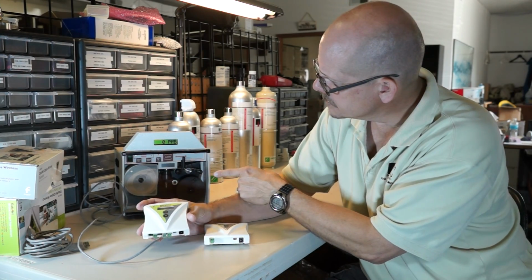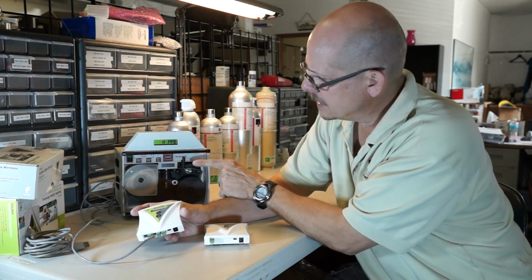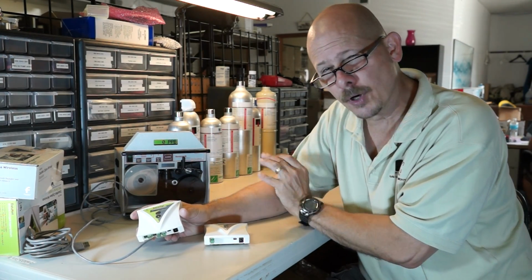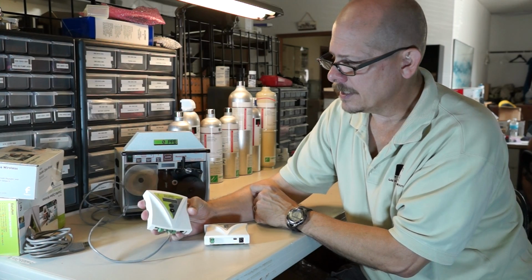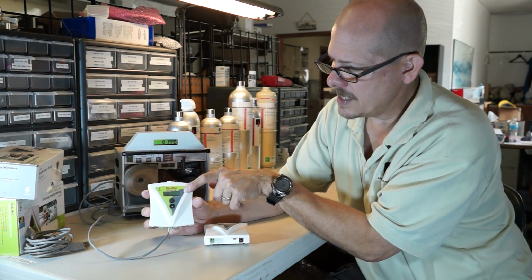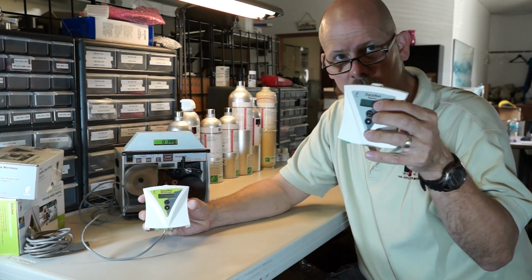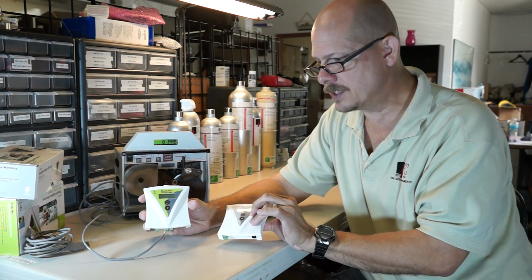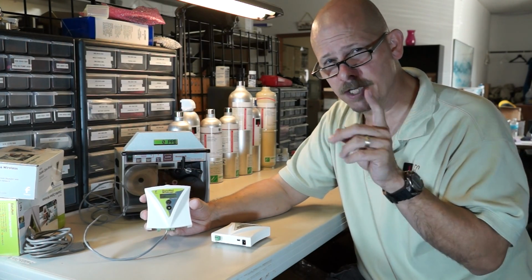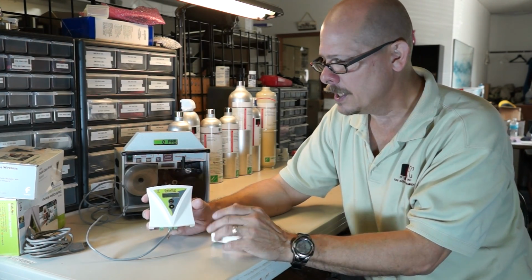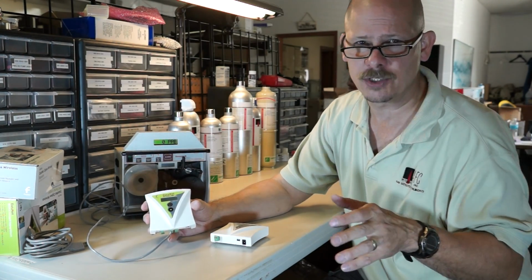And in this case here, this is the Honeywell TLD device used for isocyanate detection. But it takes that 4 to 20 milliamp signal, converts it into parts per billion concentrations. So right now we're reading 0 parts per billion, and I can easily make sure that that signal is being taken into the DataNet. And then from the DataNet, it can wirelessly send that signal to the receiver module here, which would then be connected up to your computer. And I'll go over these things in a little bit more detail as we get along in this short video. But again, the whole process is anybody's device, any kind of instrument make or manufacture from anybody.